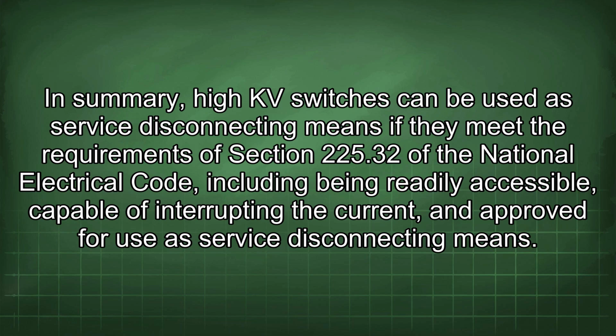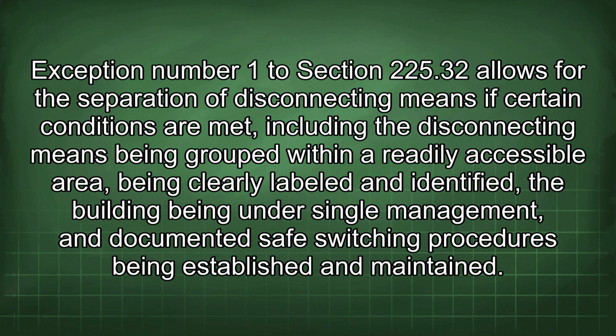In summary, high kV switches can be used as service disconnecting means if they meet the requirements of Section 225.32 of the National Electrical Code, including being readily accessible, capable of interrupting the current, and approved for use as service disconnecting means.